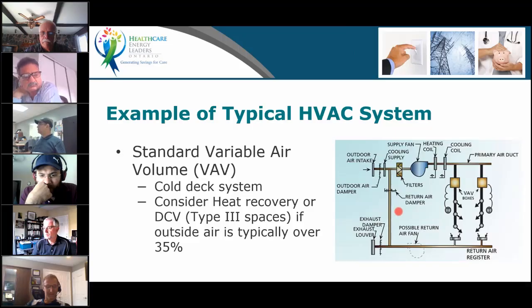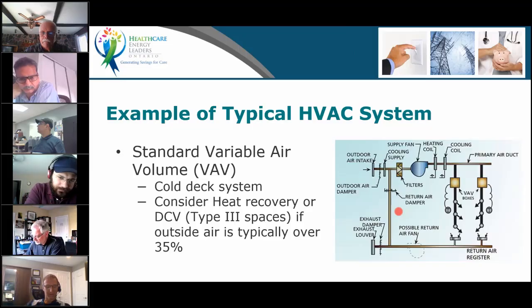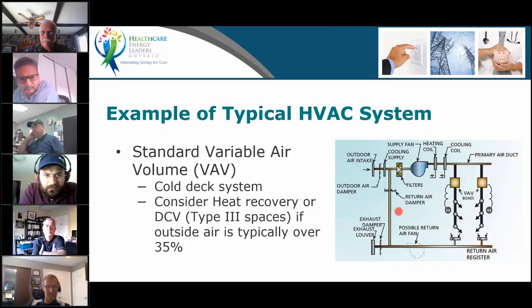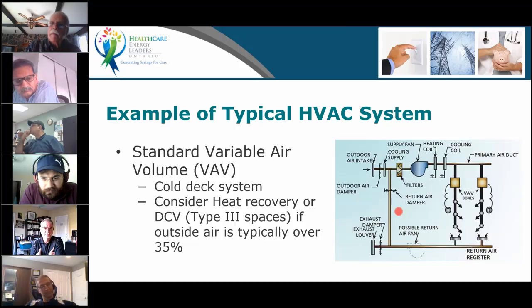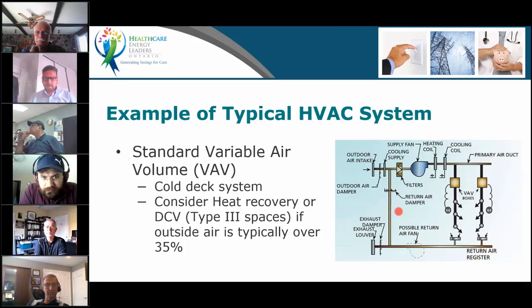If your BAS vendor comes in, says you have a VAV, and says I'm going to put CO2 sensors in every room, because you can't use a return sensor on a VAV system, that is not acceptable. You have to have zone level sensors. That's a lot of maintenance, and it will likely save you very little on a regular VAV. If you have a high percentage air VAV, yes, that becomes interesting when it's possible. You have to, again, know your regulation. Are you subject to CSA Z317.2? If so, well, DCV is restricted to just a few spaces. So that's what you need to know on your HVAC system.